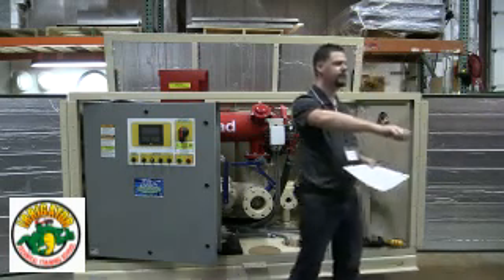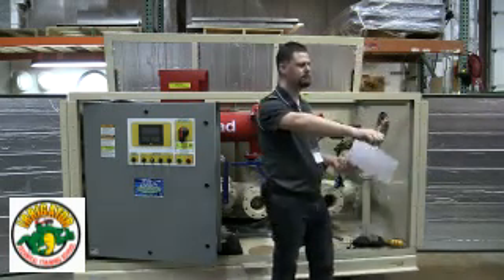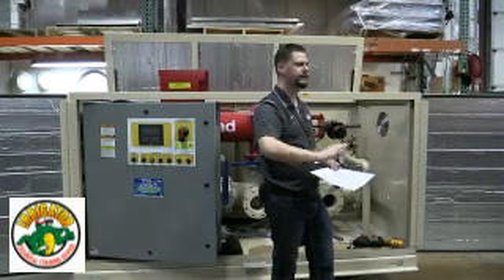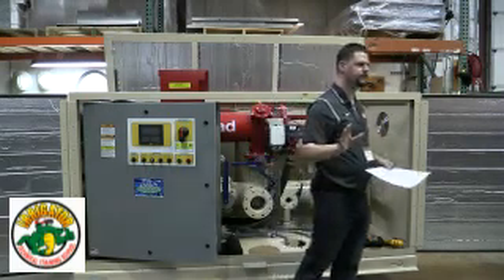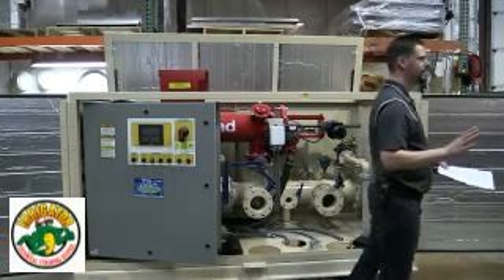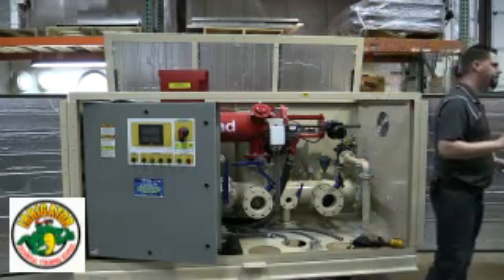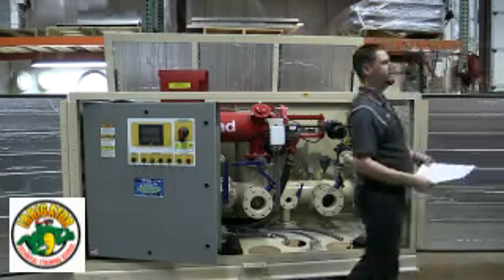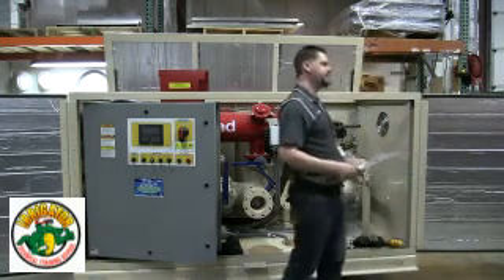Turn that puppy, it starts flushing, let it run a little bit of a cycle, turn it off. The filter is fully tested at that point. There's nothing about that filter you need to do. Is that three-way valve a spec item, or is that something you guys put on automatically? It comes on most SAF filters. It is a spec item.